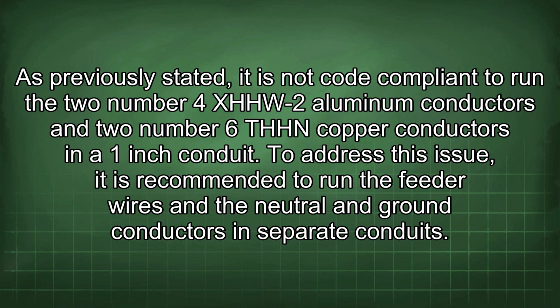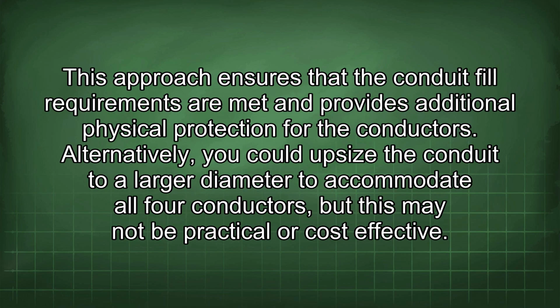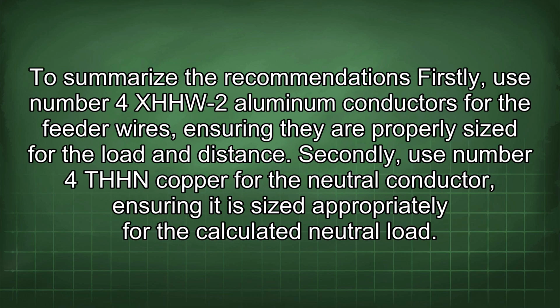As previously stated, it is not code compliant to run the two number 4 XHHW-2 aluminum conductors and two number 6 THHN copper conductors in a 1-inch conduit. To address this issue, it is recommended to run the feeder wires and the neutral and ground conductors in separate conduits. This approach ensures that the conduit fill requirements are met and provides additional physical protection for the conductors. Alternatively, you could upsize the conduit to a larger diameter to accommodate all 4 conductors, but this may not be practical or cost-effective. To summarize the recommendations, firstly, use number 4 XHHW-2 aluminum conductors for the feeder wires, ensuring they are properly sized for the load and distance.